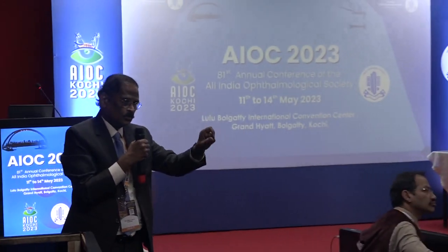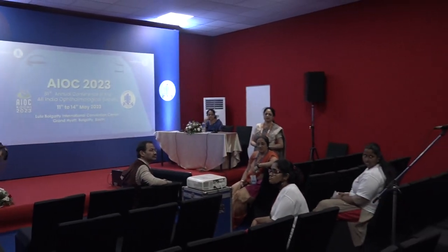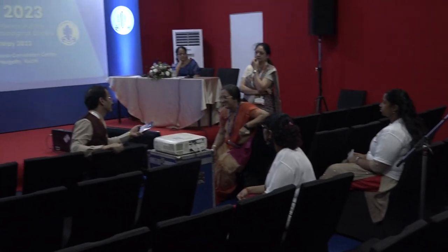Zoll are the king of the defibrillator. Every vendor who is supplying defibrillators also supplies the AED. Nowadays, apart from the defibrillator, they are also keeping the AED mode, because it may be used by a skilled man who knows everything about ECG, or by a person who doesn't know anything about ECG. So AED mode is also there in the defibrillator. It is two in one, not two in one, three in one, because the monitor is also there. You can attach the pulse oximeter, multi-parameter monitor, NIBP, everything is there, and then AED is also there.